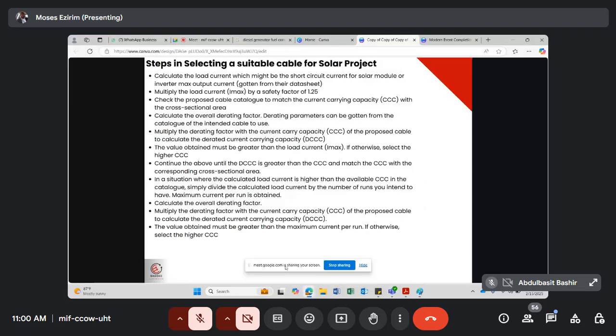So in case along the line you don't need to calculate the load current, you can use this formula, then multiply it by 1.25. So let's get to DC side battery cables. Now you write down the active power of the inverter where the cable will be terminated, alongside its battery voltage.